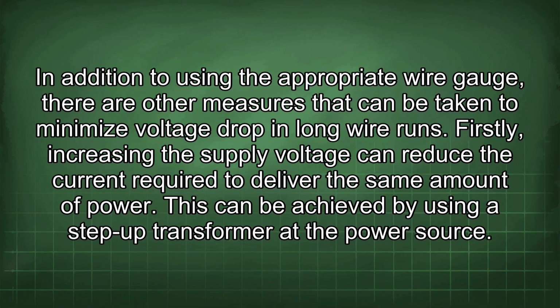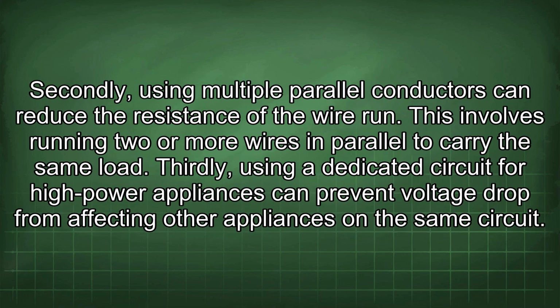in long wire runs. Firstly, increasing the supply voltage can reduce the current required to deliver the same amount of power. This can be achieved by using a step-up transformer at the power source. Secondly, using multiple parallel conductors can reduce the resistance of the wire run. This involves running 2 or more wires in parallel to carry the same load.